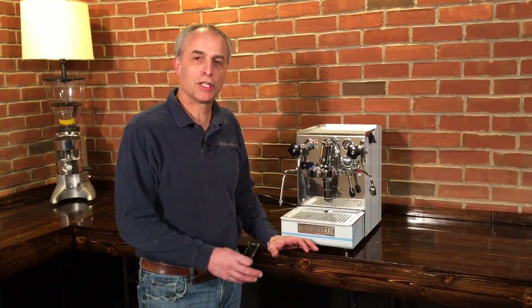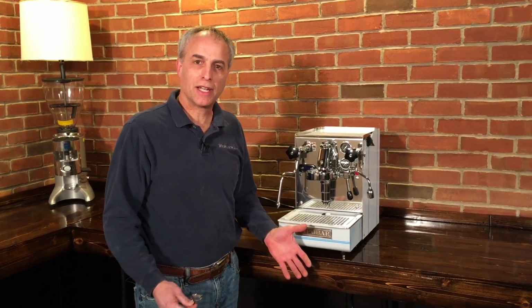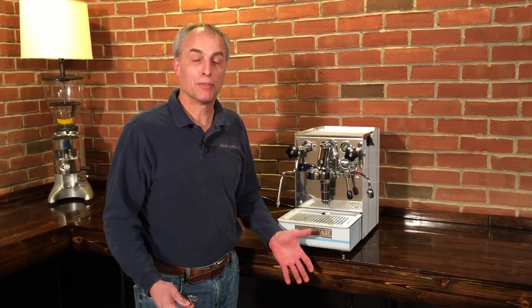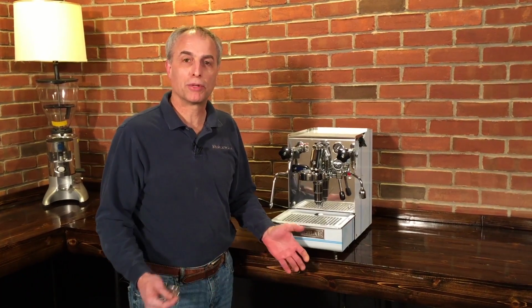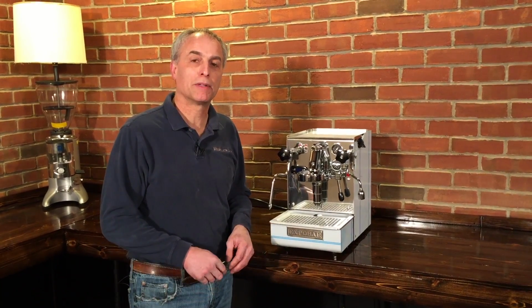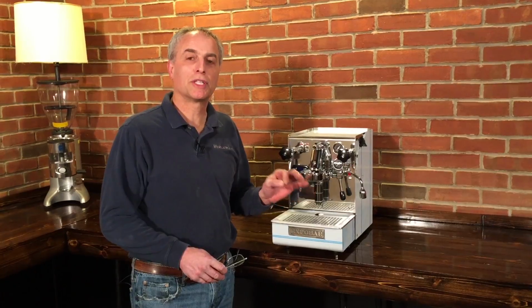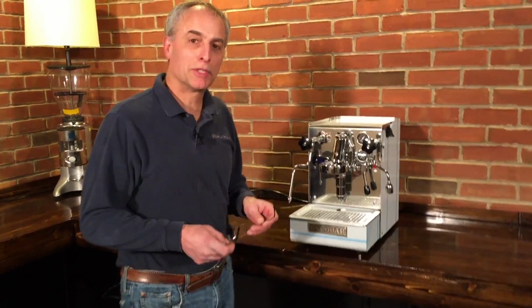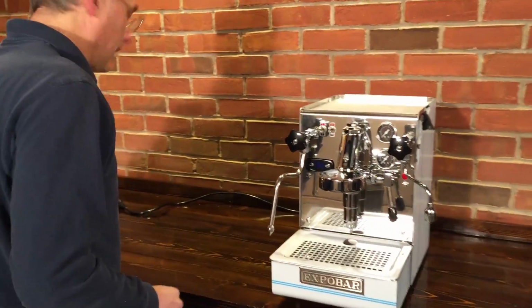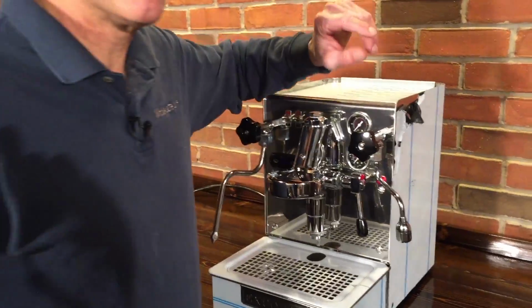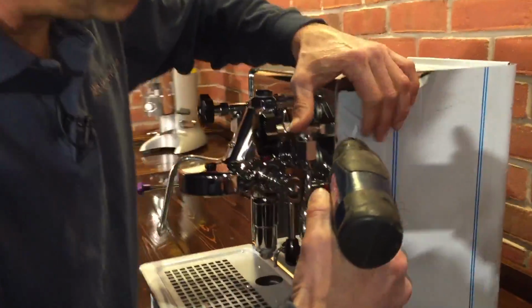Well, it could be that the water level sensor in the heat exchanger boiler is either disconnected or maybe really, really dirty. Most likely something happened and it's disconnected. If it was just dirty, you would have noticed low steam pressure or something else happening over time. So here's what you can do to check that out. We're going to go inside the machine and see if that wire from the temperature or the water probe is disconnected.